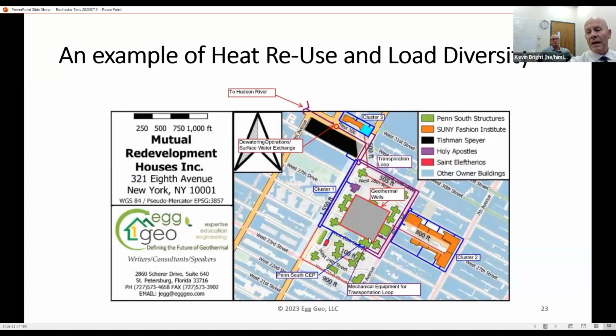They have a central energy plant with a 5 megawatt boiler to distribute heating and domestic hot water to those buildings. Once we looked into how they could be heated, we noticed there was a post office rejecting 8 megawatts of heat, even in the middle of winter, through cooling towers like you see here. We suggested funneling that energy into the central energy plant through heat pumps, and the idea was sound, so they funded the project.